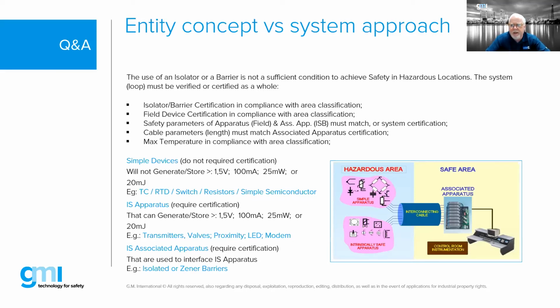The GMI barriers, as an example, are actually certified to be installed in a Zone 2 in a suitable enclosure. But if they had to go into a Zone 1, you can install the barriers in a pressurized PXB enclosure, or put them into a flame-proof Ex d type enclosure.